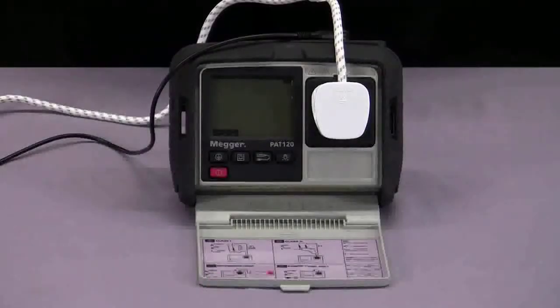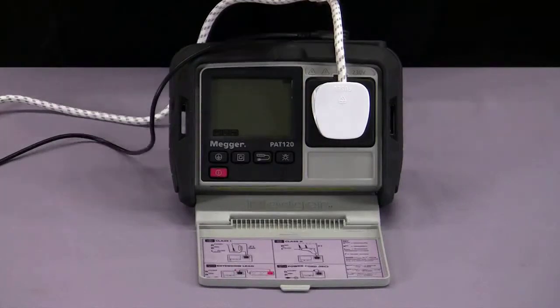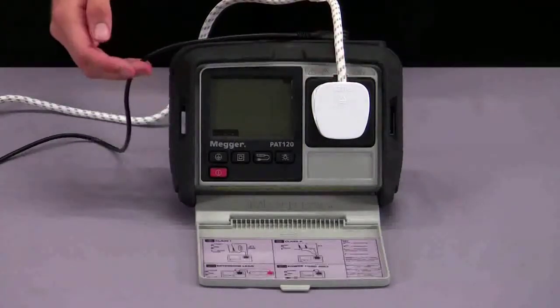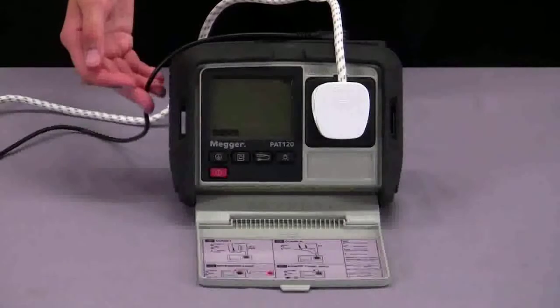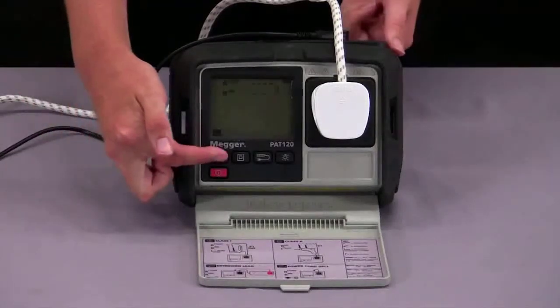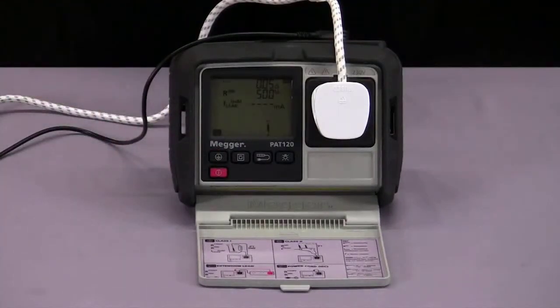For testing Class 1 equipment, I've got my appliance plugged in as well as my earth continuity lead connected. I can just press my Class 1 button and begin the test. It will perform an earth continuity test. It will then move on to an insulation resistance test. I've got it set to 500 volts, but you can select 250 volts for sensitive equipment. It will then perform an earth leakage test and indicate a pass or a fail with a tick or a cross.